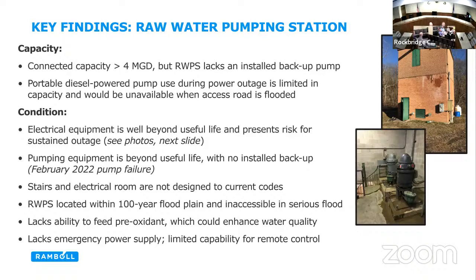And so our infield tank, one of the things that's not in this presentation but is in the report, is that even though it's a 3 million gallon tank, we only have access to around half of that at any moment because of the way it was retrofit constructed. We start to see cavitation in the pumps when you get below 15 feet of that 30 feet available volume. We've run it down to 12 feet, but that causes problems with the equipment. So a quick way of looking at it is we have about 1.5 million gallons in our infield tank, which is about a day's worth of capacity at infield.